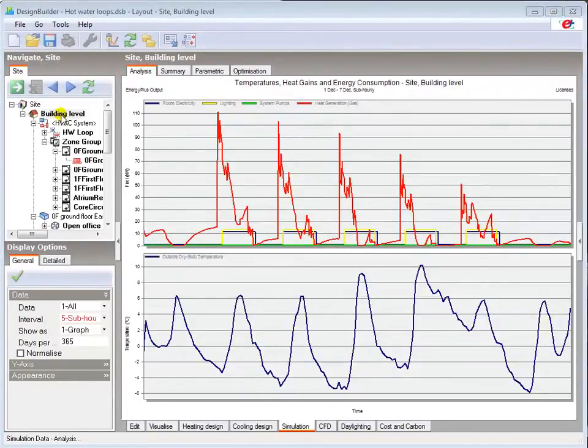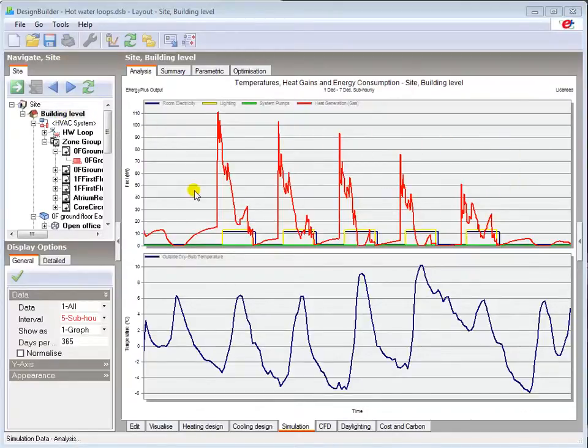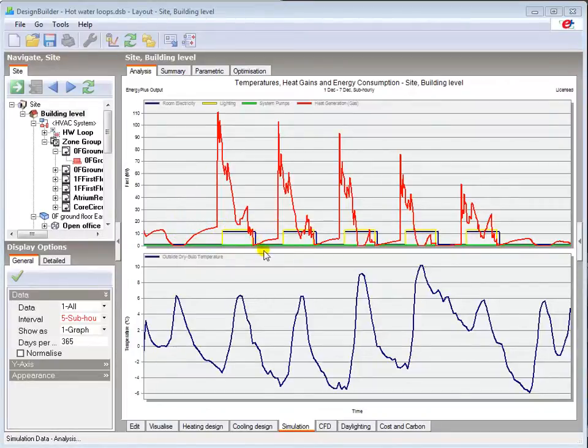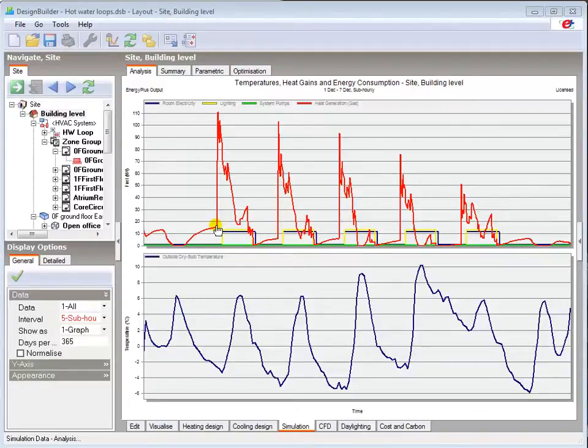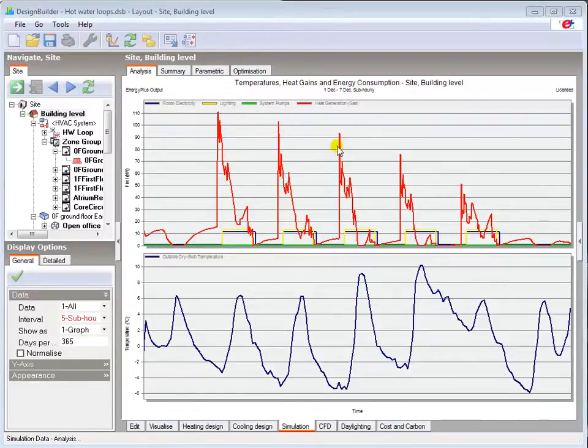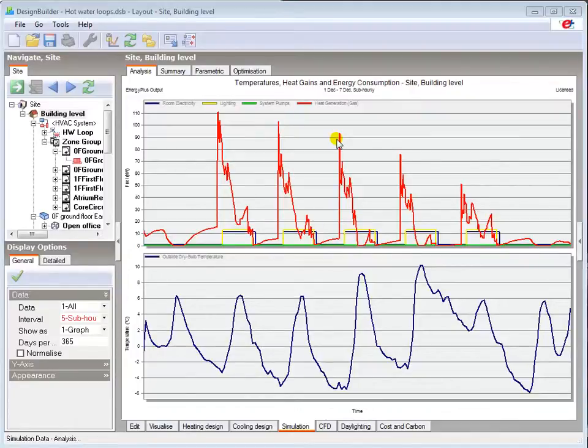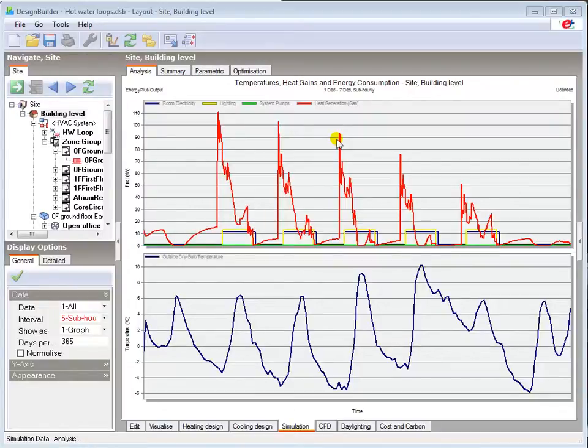At building level, the fuel consumption breakdown here shows the heating system operating in the early hours to maintain the setback temperature in the building, and then peaking to reach the setpoint temperature just prior to occupation. All of the plant availability schedules are set to on by default, so using the simple HVAC activity data, our system will operate whenever there's a demand, i.e. to meet the setpoint and setback conditions defined in the model data, activity and HVAC tabs.